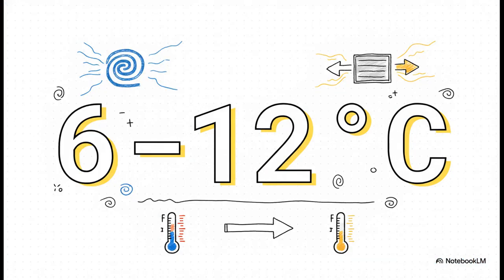So, doing the math, the crucial point is that we've got a missing 6 to 12 degrees Celsius, or an 11 to 22 degree Fahrenheit gap. The internal coil is always significantly colder than the air leaving those vents. In HVAC engineering, this missing temperature is known as the thermal transfer differential. But where does the heat actually go? Like, why doesn't the air just match the coil temperature?